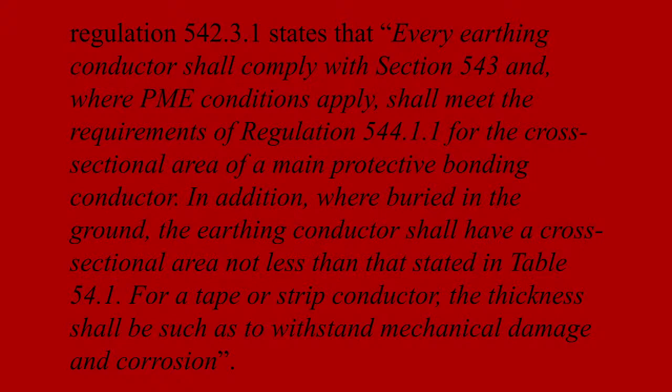We can only use the adiabatic equation if it's for TT or TN-S. Always was wrong because we can't always use it. We can't use it for PME. Never was wrong because we can use it when we're not talking about PME. And not in special locations was a bit of a red herring. There was no requirement there about special locations. So just to clear it up, the correct answer should have been D. We can use the adiabatic equation to size that protective, that earthing conductor in TT and TN-S systems.